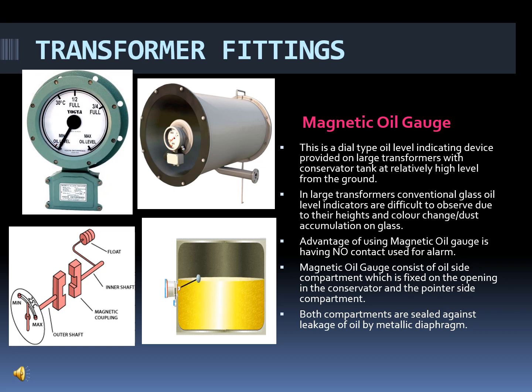Now we will discuss the fitting that is called a magnetic oil gauge. This is the dial type gauge. I have enclosed the image. This is a dial type gauge and it is an indicative device provided in the large transformers with a conservator tank at a relatively high level from the ground. In large transformers, conventional glass oil level indicators are difficult to observe because of accumulation of dust or change in color. Hence, the dial type of oil level indication will be useful. Hence, the magnetic oil gauge will be preferred in the large type of transformer.